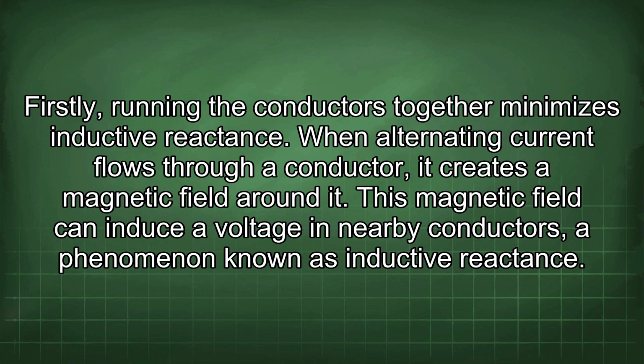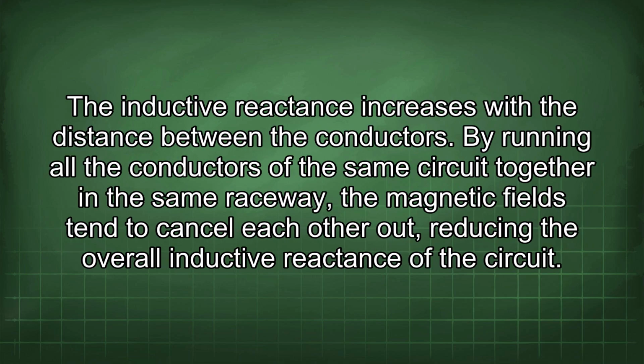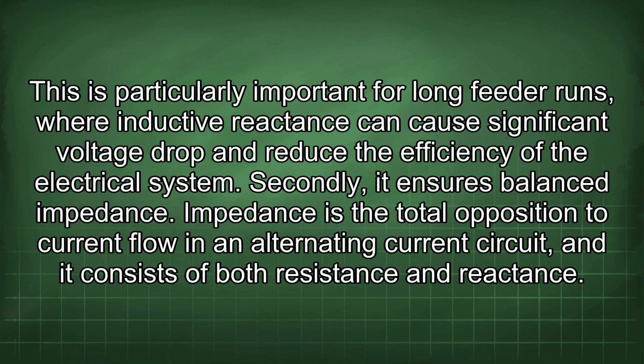Firstly, running the conductors together minimizes inductive reactance. When alternating current flows through a conductor, it creates a magnetic field around it. This magnetic field can induce a voltage in nearby conductors, a phenomenon known as inductive reactance. The inductive reactance increases with the distance between the conductors. By running all the conductors of the same circuit together in the same raceway, the magnetic fields tend to cancel each other out, reducing the overall inductive reactance of the circuit.